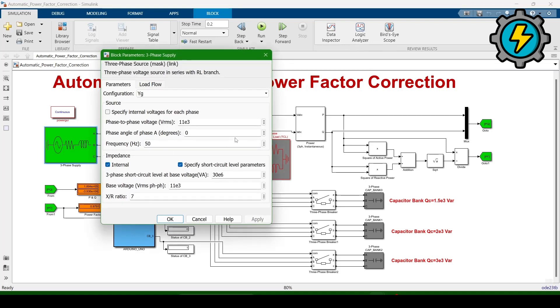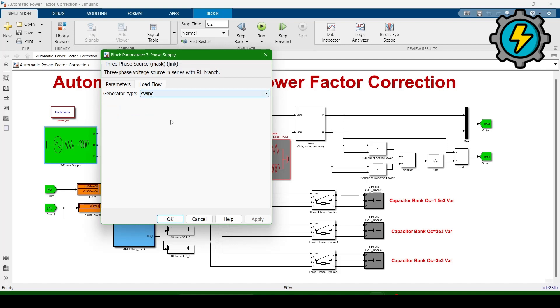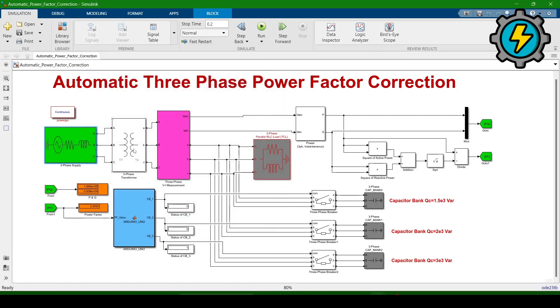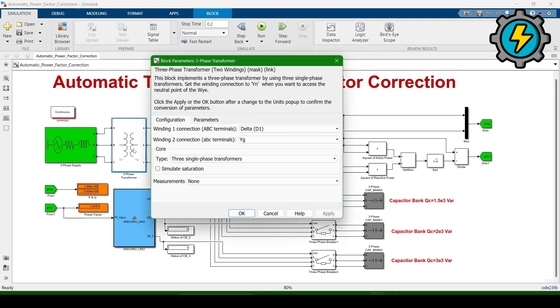Double click on the three-phase supply. Here the phase-to-phase voltage is 11 kV, the three-phase short circuit level at base voltage is 30 MVA, base voltage RMS phase-to-phase is 11 kV, the X/R ratio is 7, and the load flow is swing type. Now double click on the three-phase transformer to see its values.